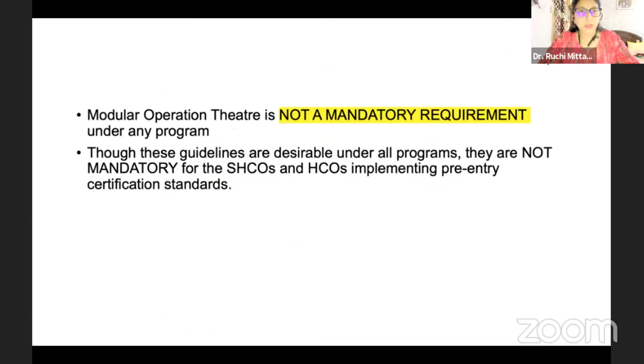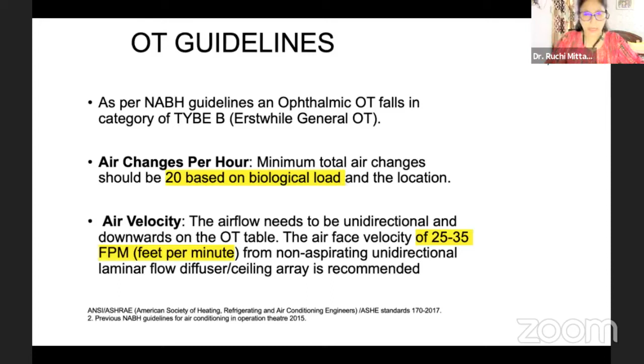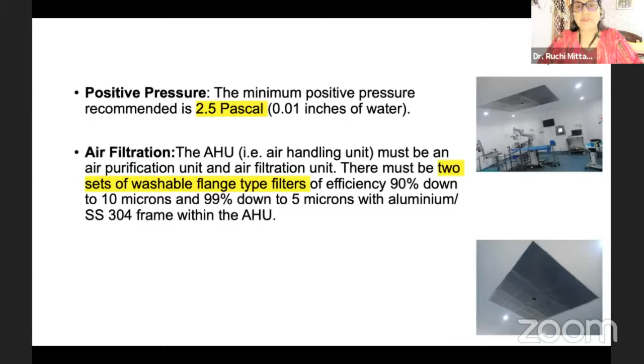Now, as per the NABH guidelines, ophthalmic OTs fall in the category of type B. The air changes recommended per hour are 20, involving 4 fresh air changes. Air velocity should be 25 to 35 feet per minute, and it should be unidirectional and downward towards the OT table. The minimum positive pressure recommended is 2.5 pascals, and the air handling unit, which is an air purification and filtration unit, must have 2 sets of washable flange type filters.